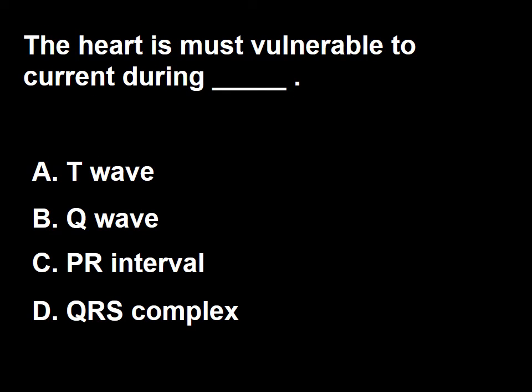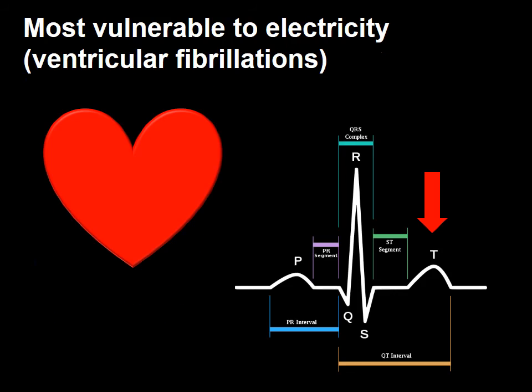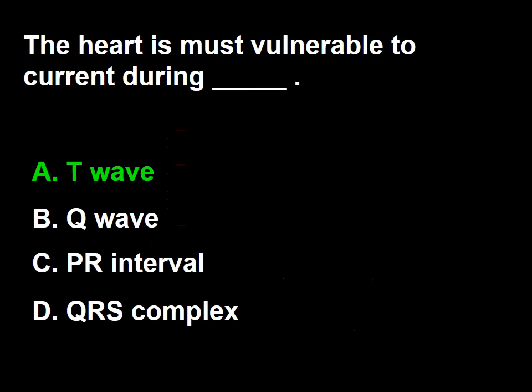Next question: what is the resistance from the tip of a central catheter with an internal guide wire to the heart? A: 10 million ohms, B: 300 ohms, C: 2,000 ohms, D: 70 ohms. The resistance from the tip of a central catheter to the heart is about 70 ohms. So the answer is D. Next question: the heart is most vulnerable to current during which part of the cardiac cycle? A: T wave, B: Q wave, C: PR interval, D: QRS complex. The heart is most vulnerable during the T wave, so the answer is A.